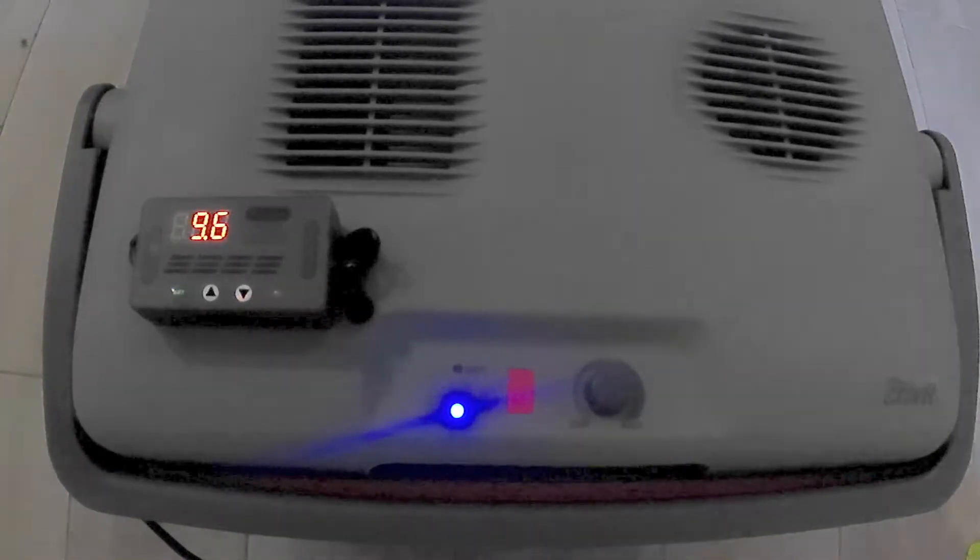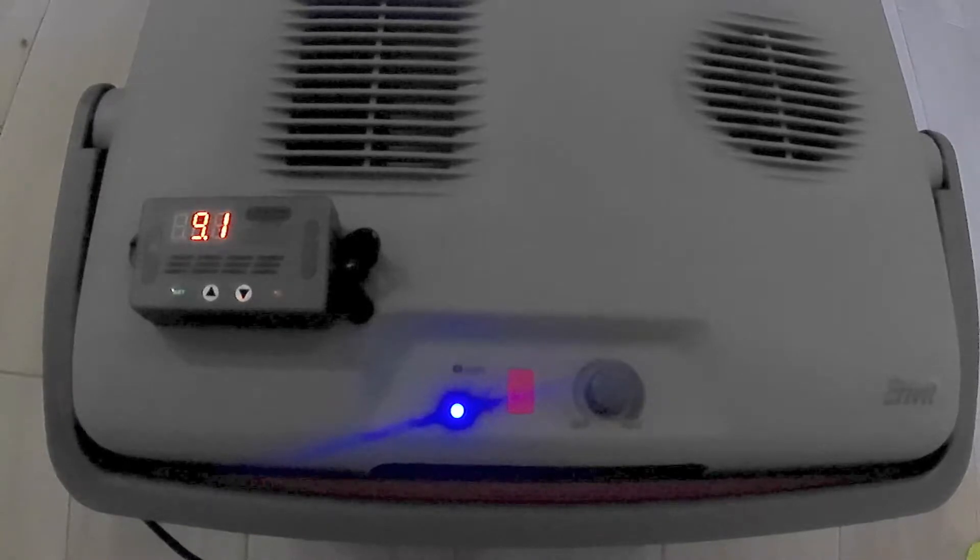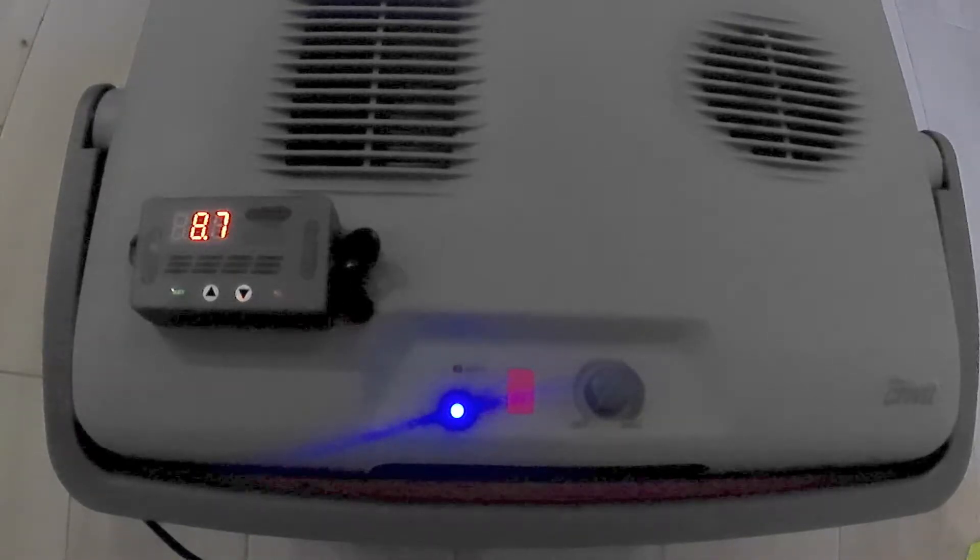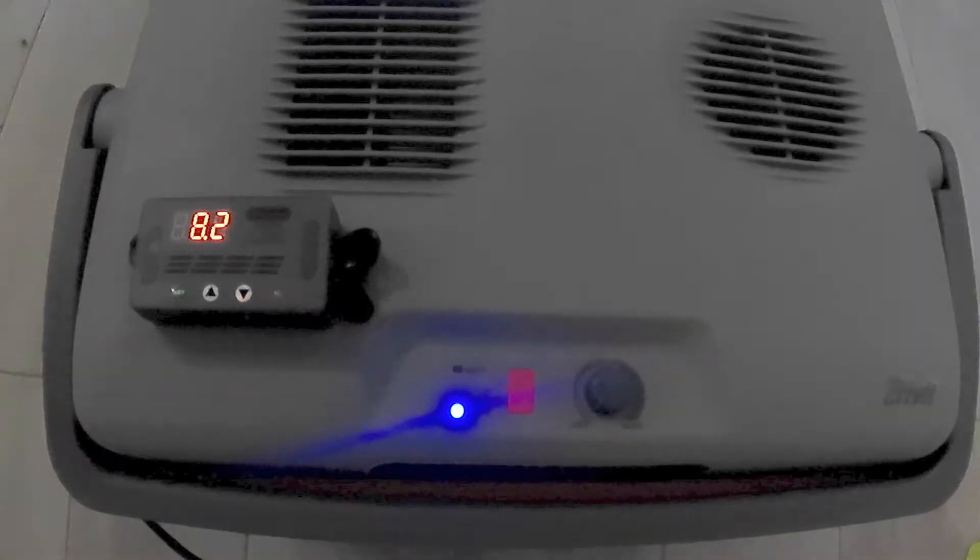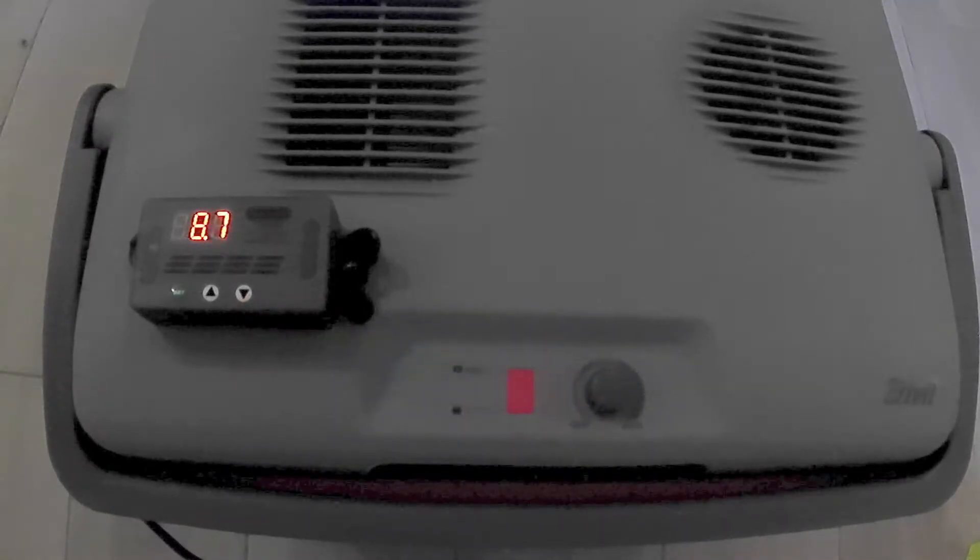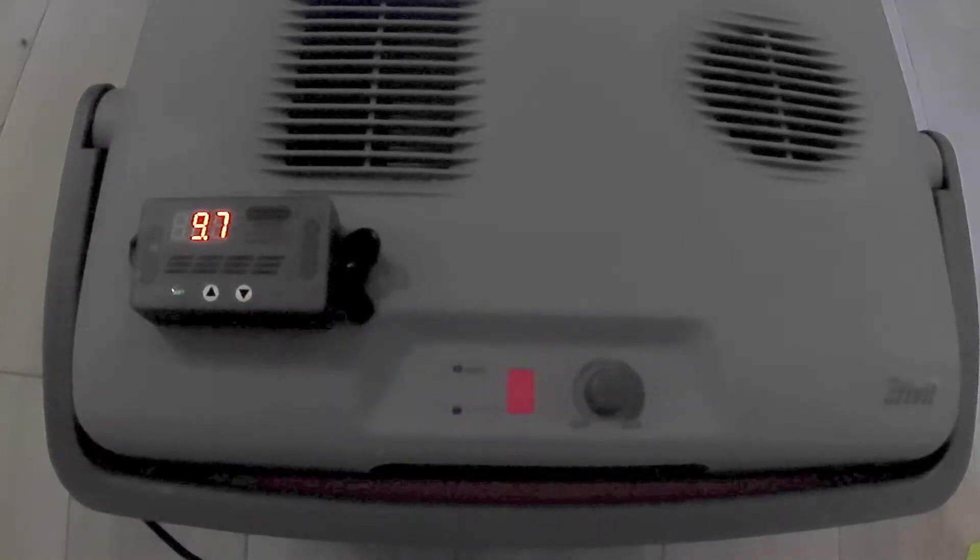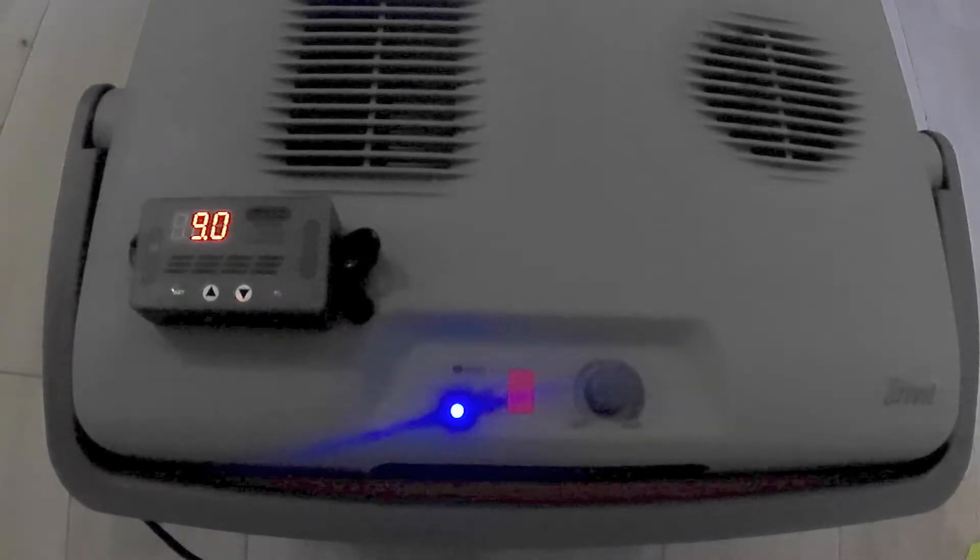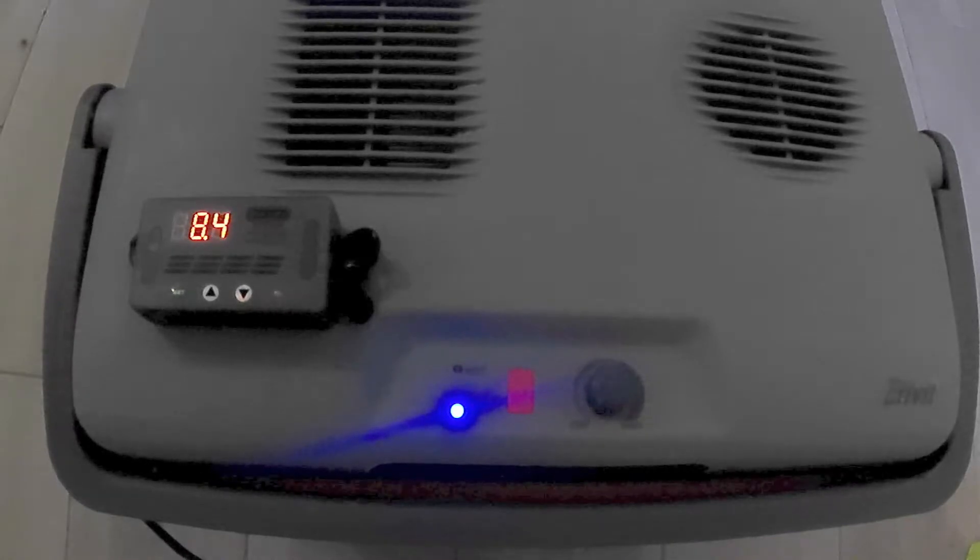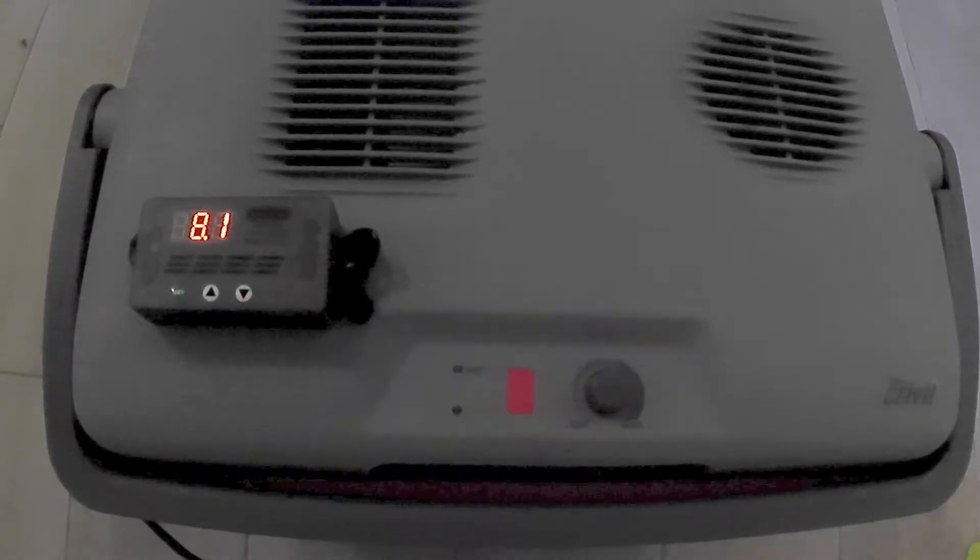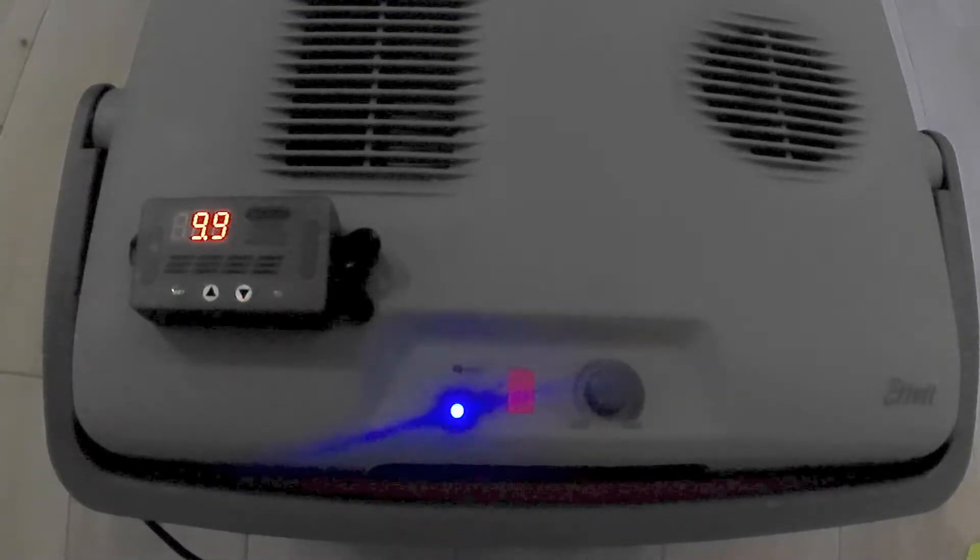So this is just a bit of a time lapse to show you it's actually going down. I set it to 8 degrees to turn off and then it creeps back up and then it starts again at 10 degrees. And that's just a 2 degree difference and that's inherent in the thermostat as you get it. So it's just the lowest temperature you set.